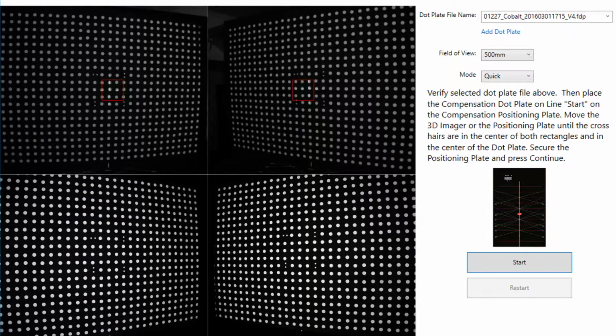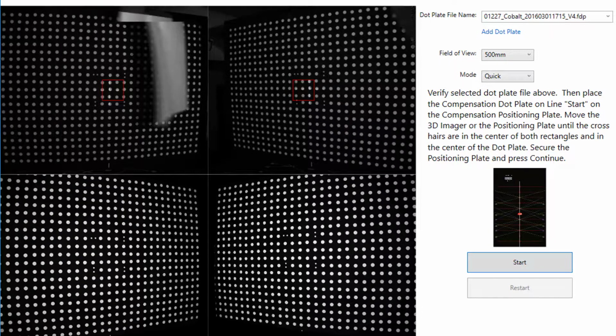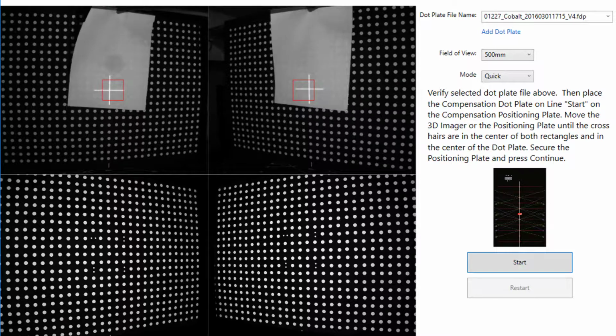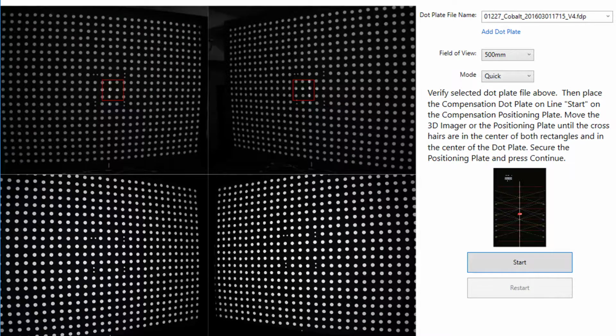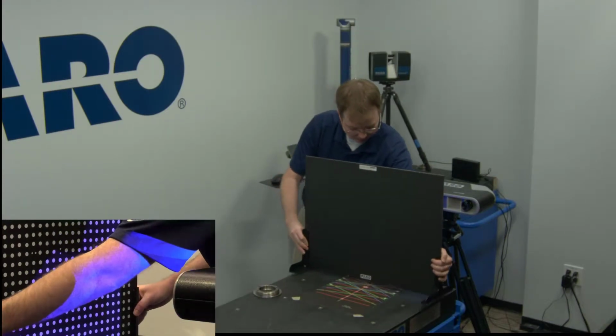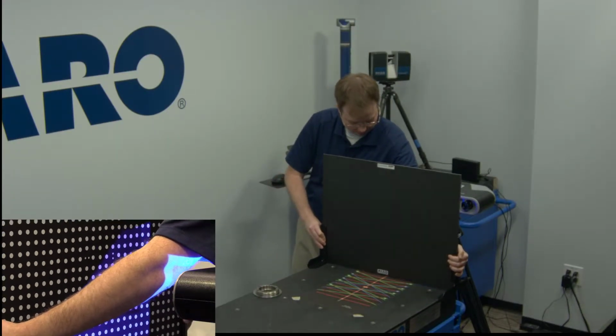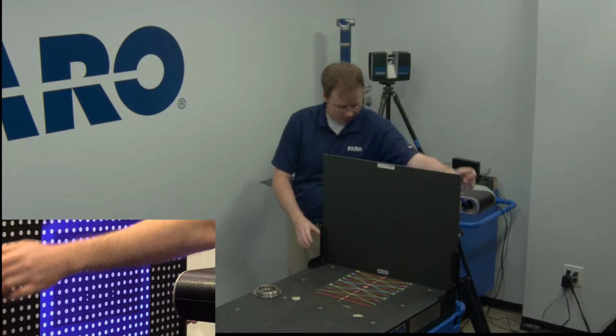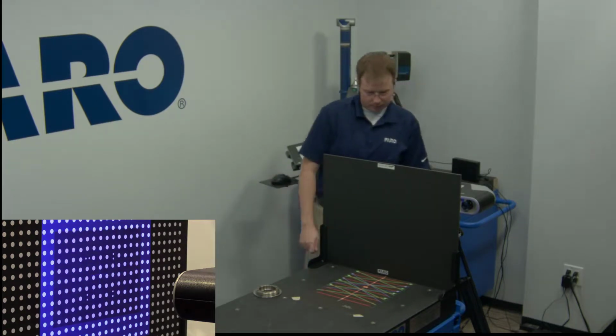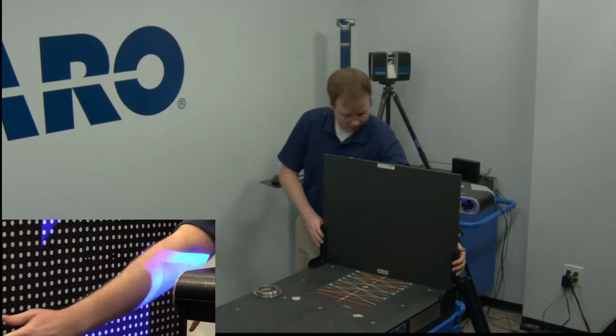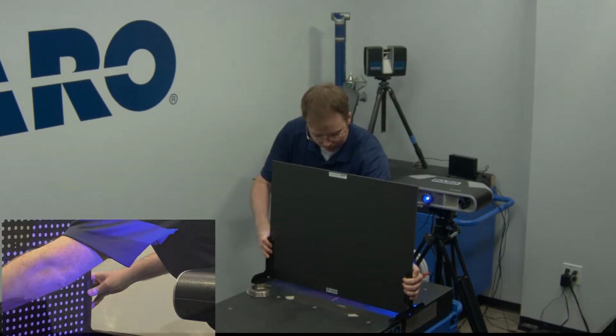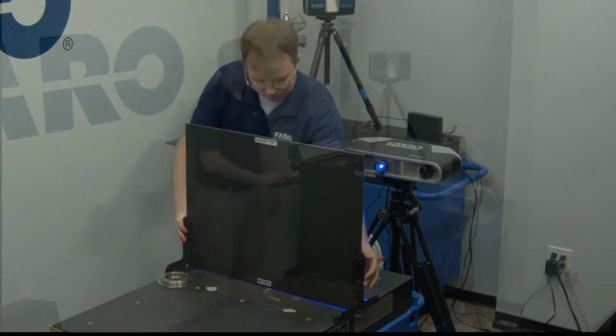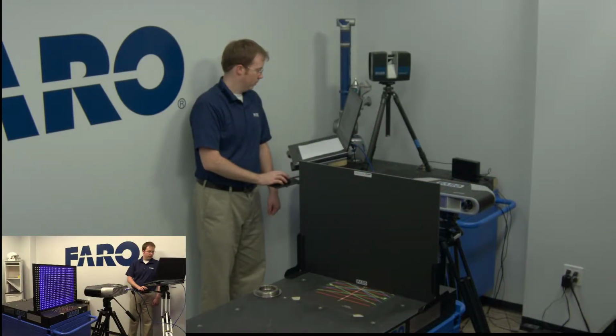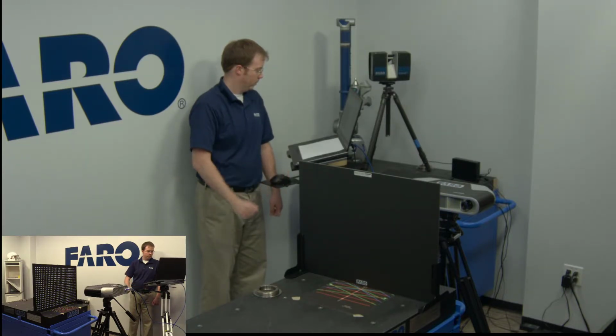Note, if the crosshairs cannot be seen clearly, hold a white sheet of paper directly in front of the calibration plate. To verify that the Cobalt and the dot plate are in the correct position, the dot plate can be moved to the closest position and then to the furthest to ensure the crosshair is in the exact same position on the dot plate. Once this distance between the Cobalt and the calibration plate has been set, click Start on the screen.